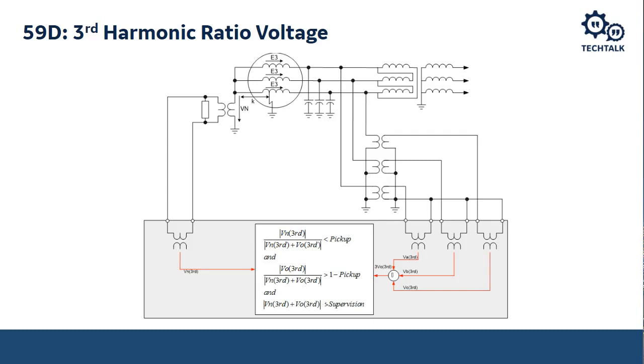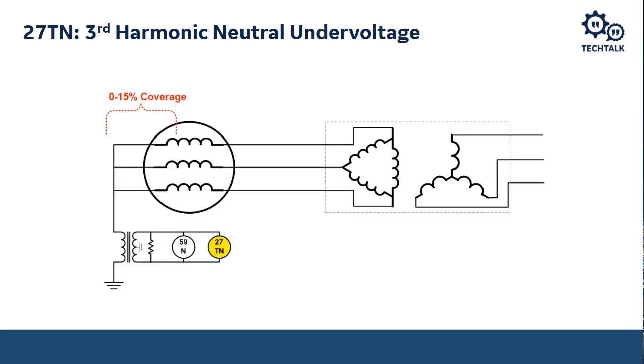One thing with the 27TN, it's very difficult to set, because first we have to know what levels of third harmonic are present when the generator is running. And there are cases, when the generator is running at certain power factors, certain load pockets, where that third harmonic voltage will fluctuate, might even drop to 0. That can cause a misoperation of the 27TN element, so you need to take that into consideration.